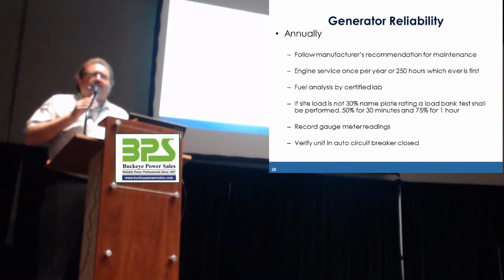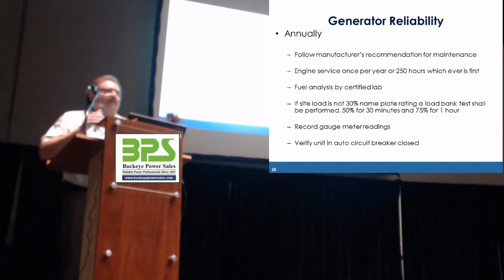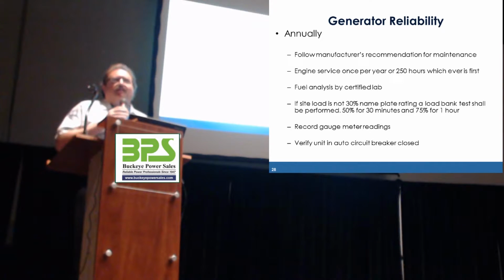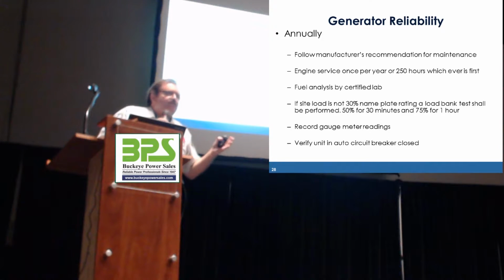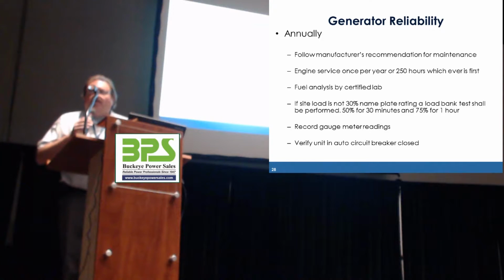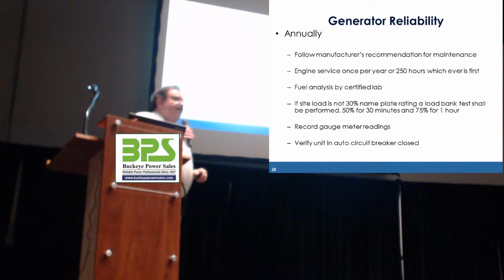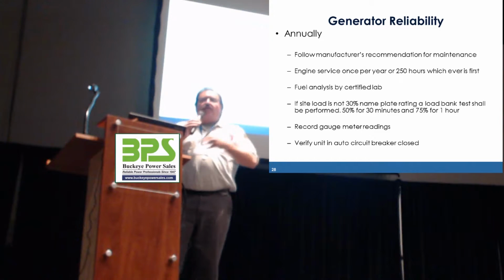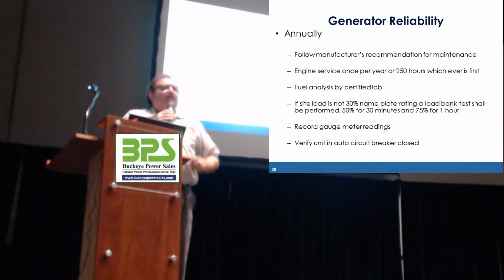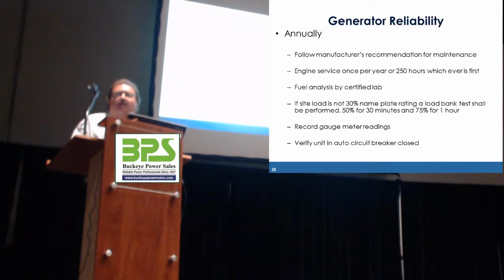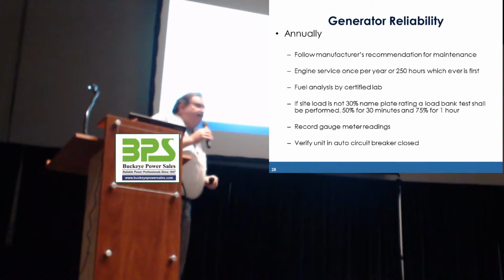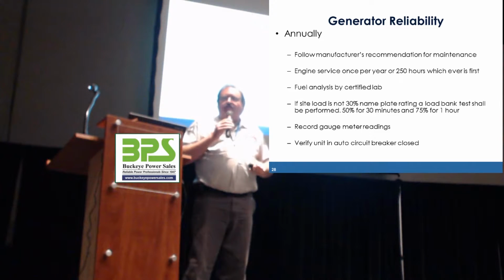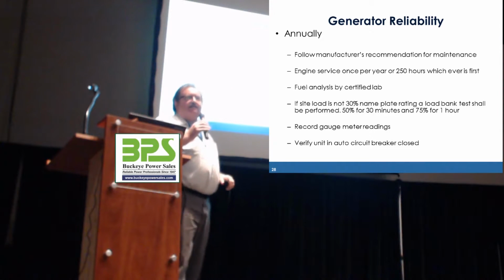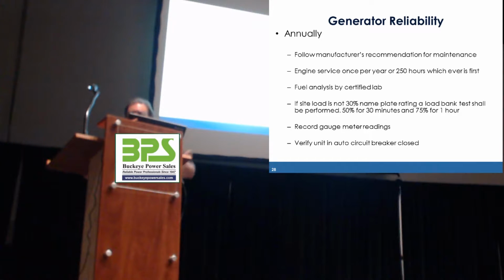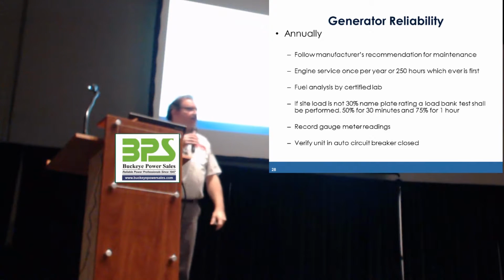Now, for healthcare, it's kind of a sticky thing. If you happen to have a spark-ignited generator that runs on natural gas or propane, the older code gives you the option, if you don't have 30% nameplate rated load, of doing the load bank test. In the spark-ignited section, it doesn't give you that option. It says you shall exercise it once a month at 30% nameplate rated load.